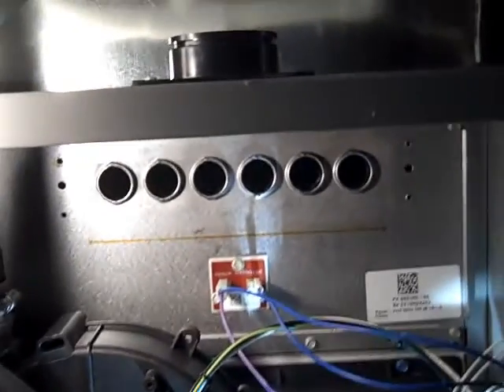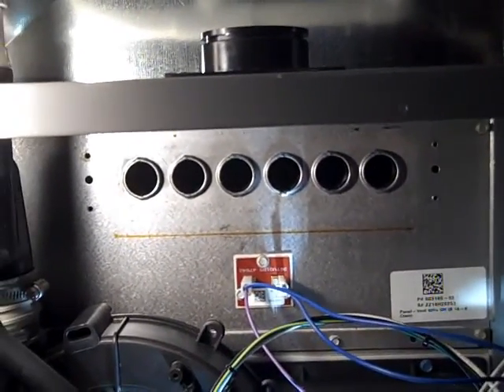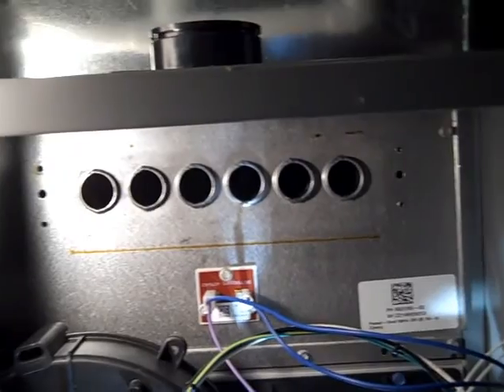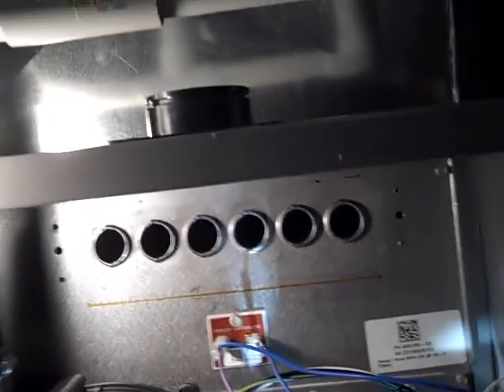As you can see, Kevin has pulled the burner box out. There are the tubes for the heat exchanger, and what we're going to see right here is the actual burners themselves. You can see the flame sensor right there, and the burners right there. He's going to pull these out to inspect them, make sure there's no problems on the sides, get to the flame sensor easily, and make sure they're nice and clean. They have to be clean.